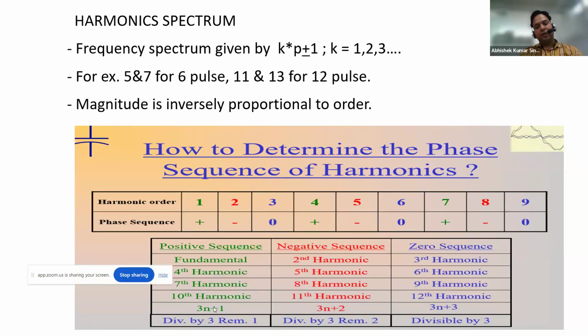Generally in single phase loads, I'm not saying in all, generally in single phase loads we find zero sequence harmonics, which are also called triplen harmonics. If you've heard the word triplen, triplen means divisible by 3. So 6, 9, 12 can all be divided by 3. So these are all triplen harmonics, and they are also called zero sequence harmonics. I believe this is clear to all. And there is one more point, in case you want to find directly whether it is positive, negative, or zero, it is very easy.